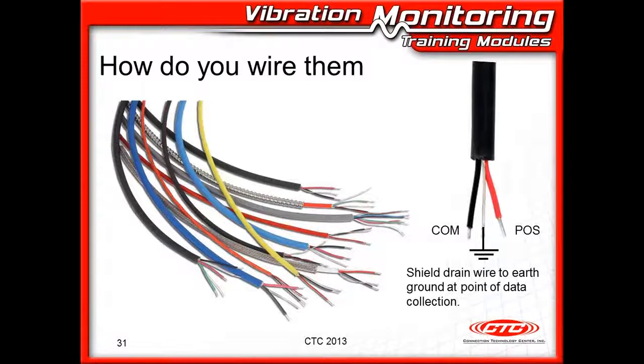We've got a lot of wiring that's available, and this is probably a whole webinar on its own. Just briefly, different wires or different cables are produced based on the application, whether it's hot and cold, dry and wet, or chemicals have become a big player as more and more things go online. So a tremendous amount of different cabling is available, and a lot of that's been driven by the chemicals that we're encountering. One thing that is true with every cable, inside of this cable you have a shield. It could be a foil shield or it could be a braided shield. That shield's there again to protect you against electrical noise.